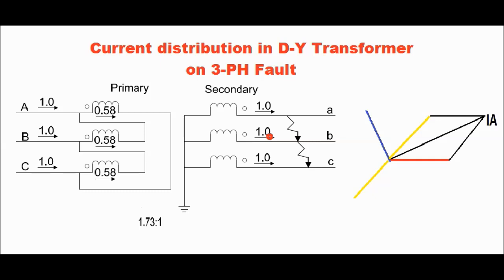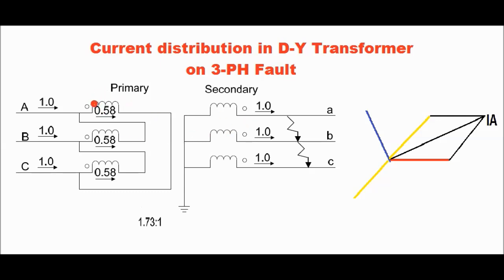Let us first discuss current distribution for a delta-star transformer on a three-phase fault in the star side winding. In this figure you can see a three-phase fault occurs, and for ease of calculation let us consider the fault current is 1 ampere for each phase — so 1 ampere flows in the red, yellow and blue phase each. Since the turns ratio is 1.73 to 1, and V1/V2 = 1.73, the current in the HV side red phase winding will be 1 divided by root 3 (1/1.73), which comes to 0.58 ampere. So 0.58 ampere flows in each phase of the primary delta side winding.